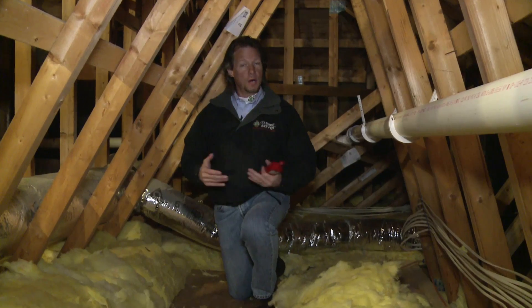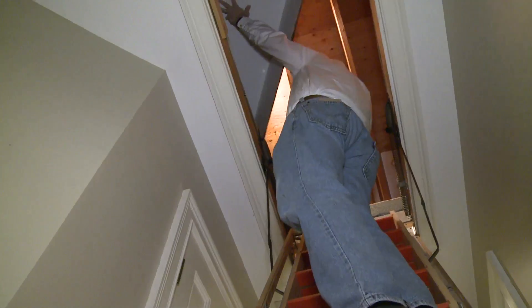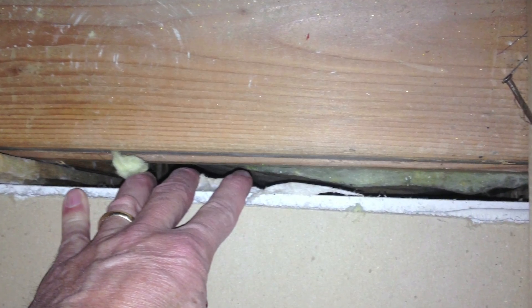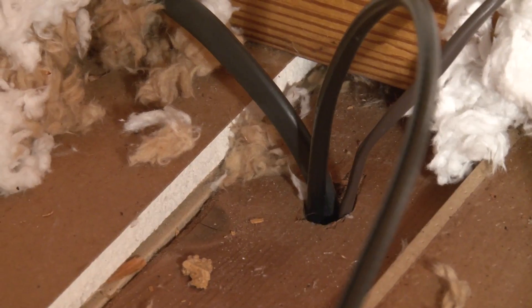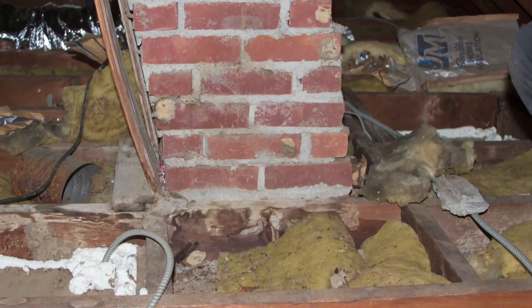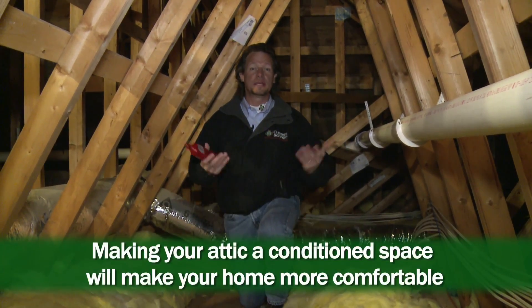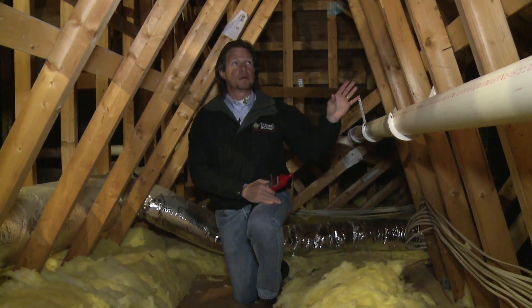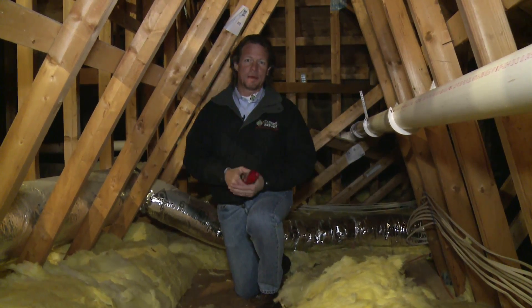Traditionally, we would go into a home and seal all the leaks in the ceiling — can lights, the attic pull-down stairs, the top of walls, interior walls where they meet the ceiling, wire penetrations, pipe penetrations, around the chimney, around the fireplace flue. We have lots of places where air can leak into the attic and typically we would seal all those. But in this house we're making a different decision — we're going to put the thermal and air barrier on the roof. In other words, we're going to make the attic a conditioned space.